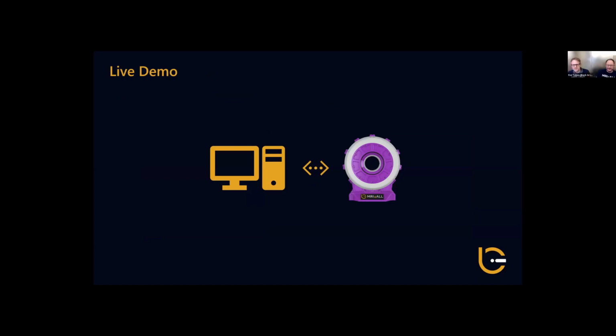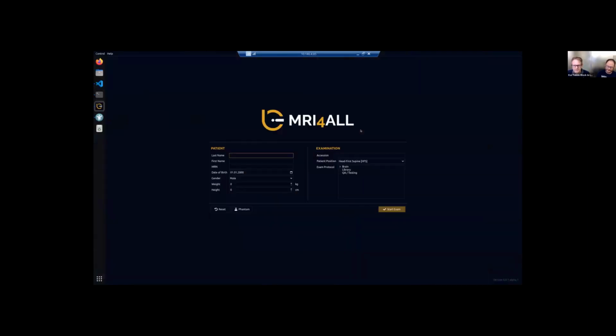So we thought it might be interesting to give a quick live demo of the scanner. The scanner is now sitting in this lab on 22nd Street in a shielded room, and we can remotely connect to the console computer and show you how the software looks and how the experience feels. So I'm quickly typing in the password. Basically, if you go to the scanner and start the scanner, you first get to this screen where you have to register a patient, similar to how it's done on a commercial scanner, where you would type in the patient name, whatever. You can also press this phantom button here to pre-populate the data.